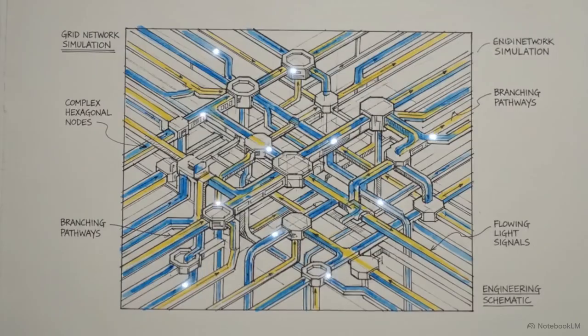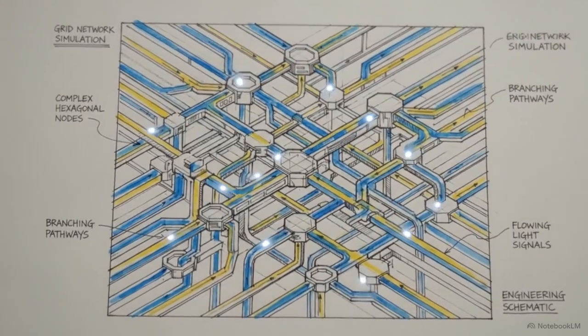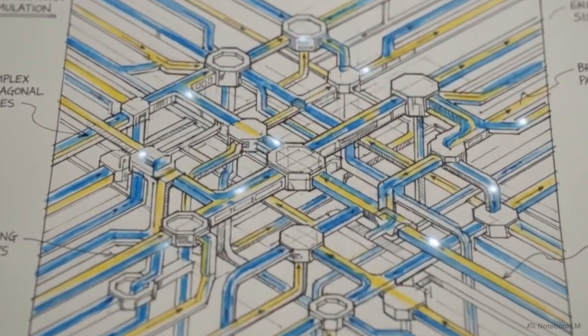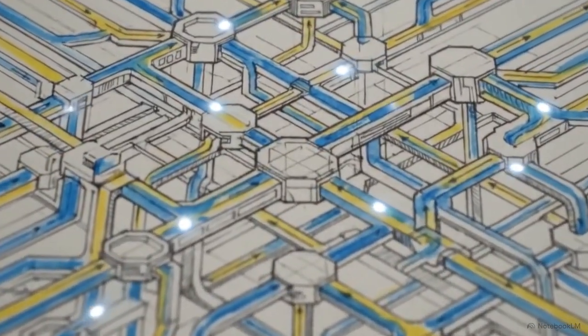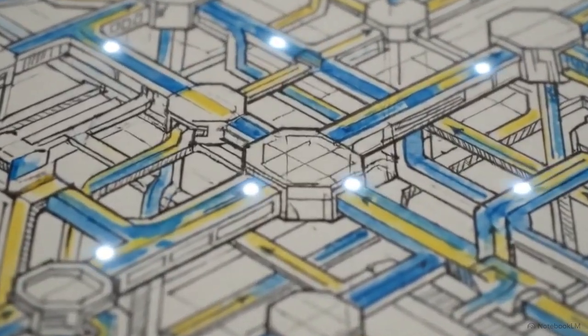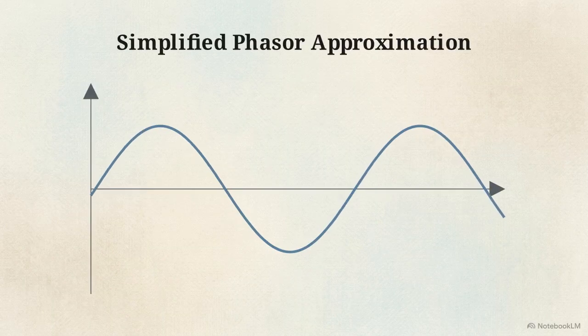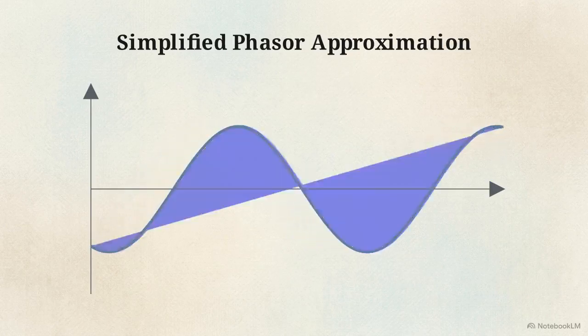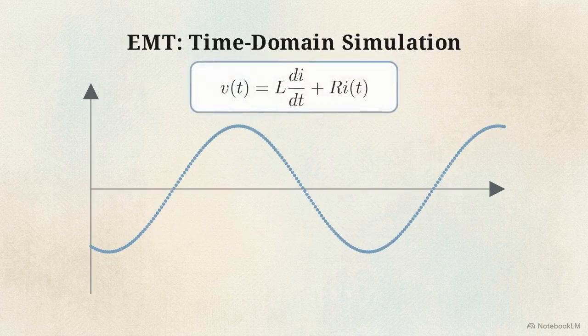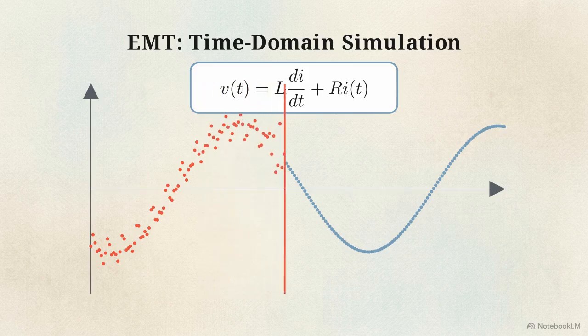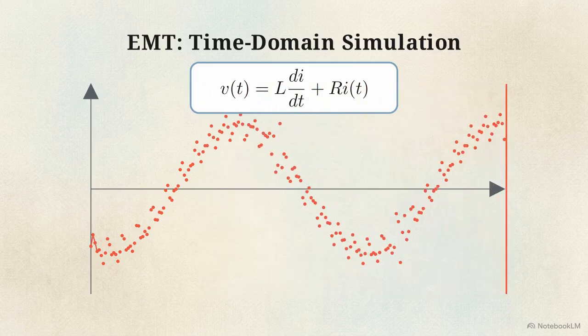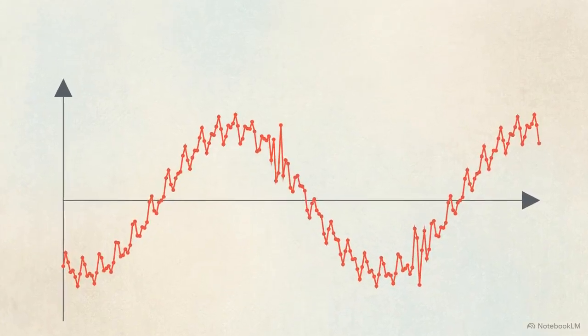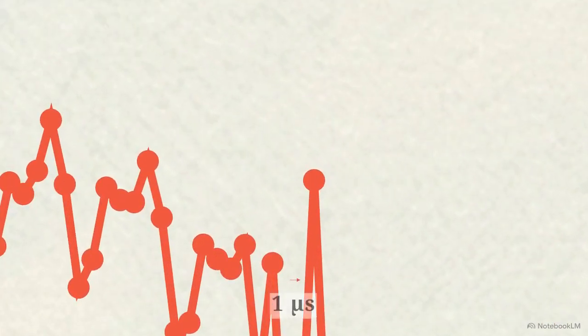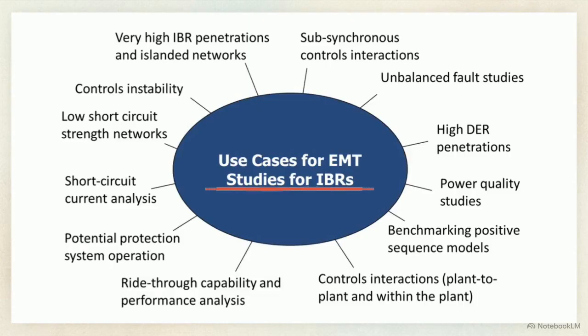Fixing this blind spot requires abandoning steady-state math entirely in favor of a much heavier computational approach, electromagnetic transient, or EMT, modeling. Instead of relying on simplified phasor approximations, EMT drops the assumption of a balanced sine wave. EMT software solves the entire system's actual differential equations in the time domain. It computes the exact voltage and current behavior point by point, calculating the true electrical waveform at incredibly small microsecond intervals. This diagram illustrates the specific use cases for EMT studies.